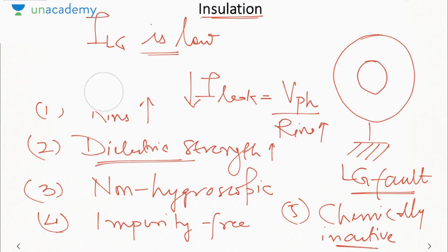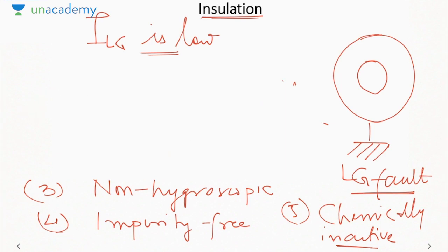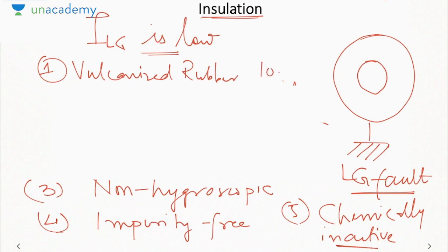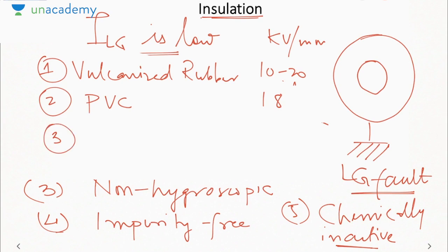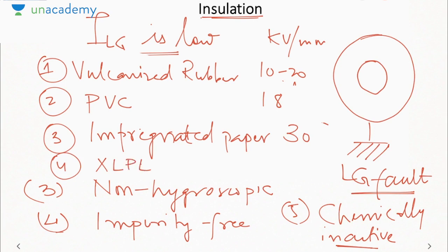Now, what are the most common materials that we use? The first material that we use is vulcanized rubber. Its dielectric strength is 10 to 20 kV per mm. Next material that we use is PVC, that is polyvinyl chloride. Its dielectric strength is 18 kV per mm. The next is impregnated paper. Its dielectric strength will be 30 kV per mm. And the last is XLPE, where X implies cross linked polyethylene, 20 kV per mm.